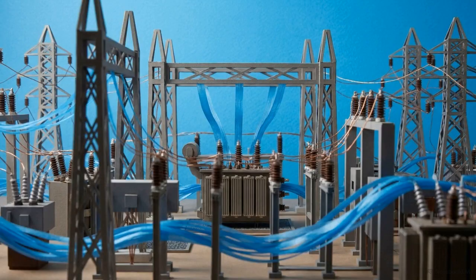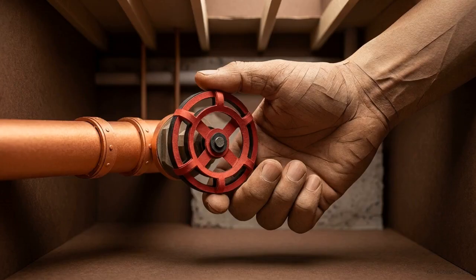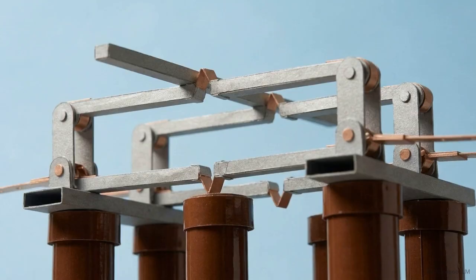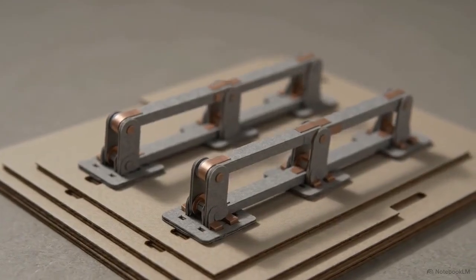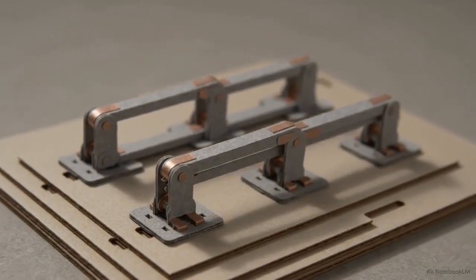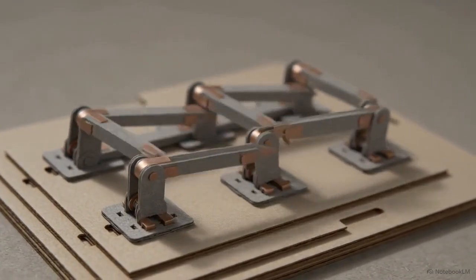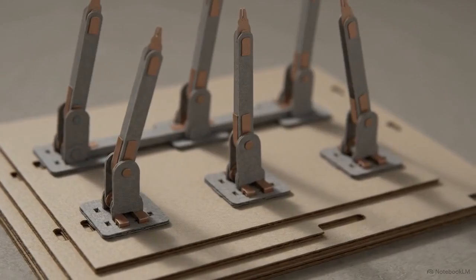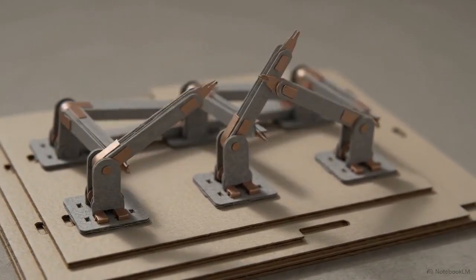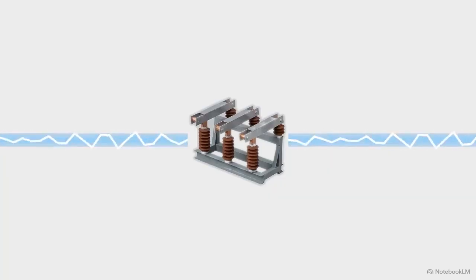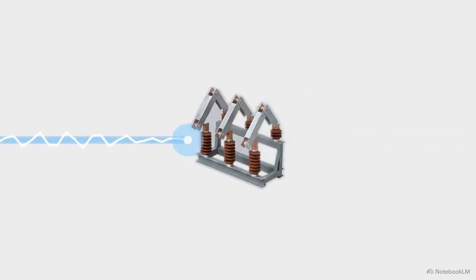Once the power is inside the yard, operators need a way to turn it off safely, much like shutting off a main water valve before fixing a pipe in your house. For this, they use a massive shutoff switch. Instead of twisting a knob, 3 long metal arms physically swing wide open. This creates a large, visible gap of empty air, completely severing the stream of high-voltage energy.